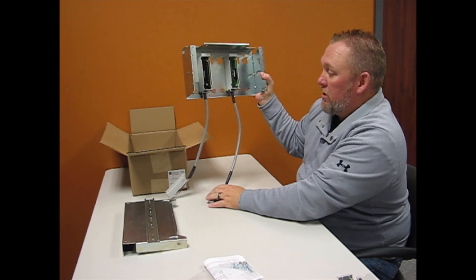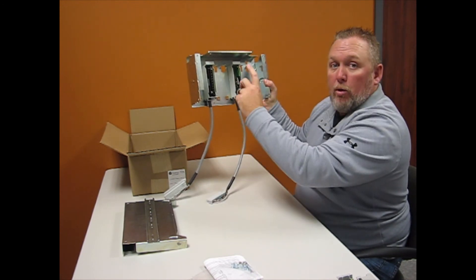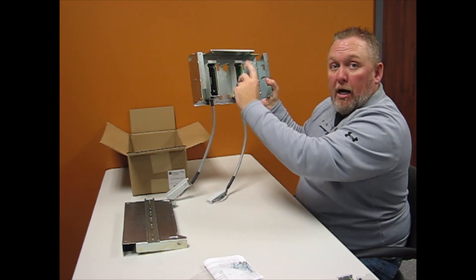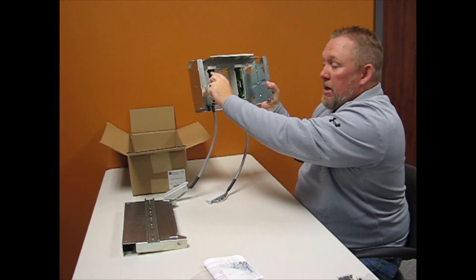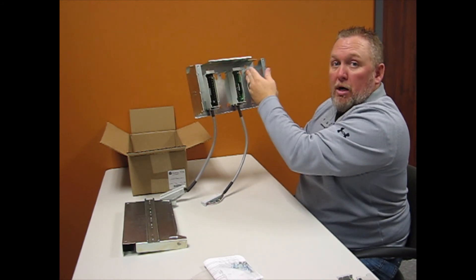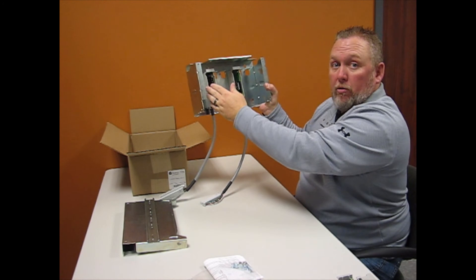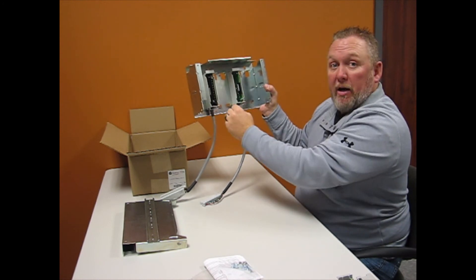Once you have the conversion modules locked into place, you will take the terminal blocks out of the SLC 500 I/O and plug them in here. So make sure you stay in order of the IO cards that you have in your SLC Rack that you are going to use on your Compact Logix.